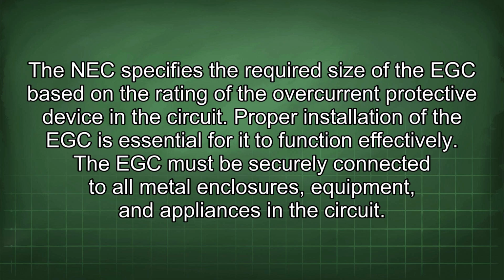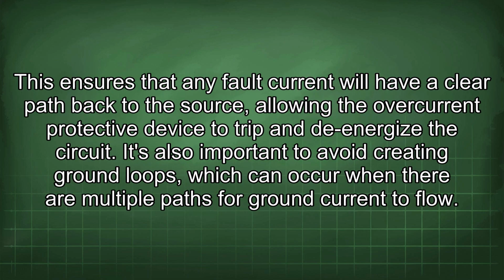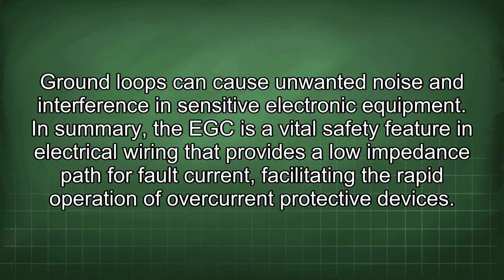The EGC must be securely connected to all metal enclosures, equipment, and appliances in the circuit. This ensures that any fault current will have a clear path back to the source, allowing the overcurrent protective device to trip and de-energize the circuit. It's also important to avoid creating ground loops, which can occur when there are multiple paths for ground current to flow. Ground loops can cause unwanted noise and interference in sensitive electronic equipment.